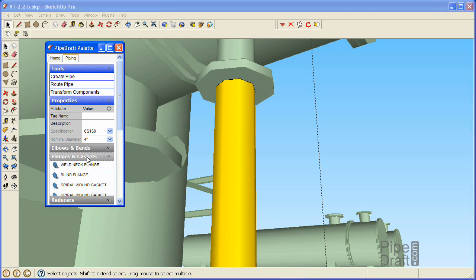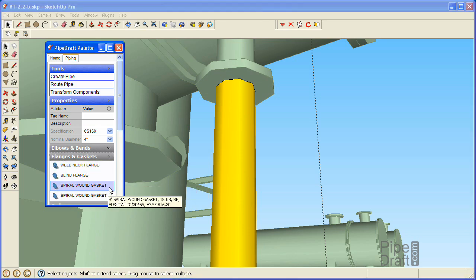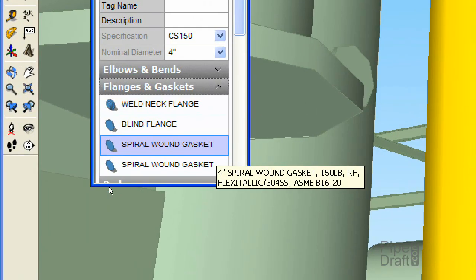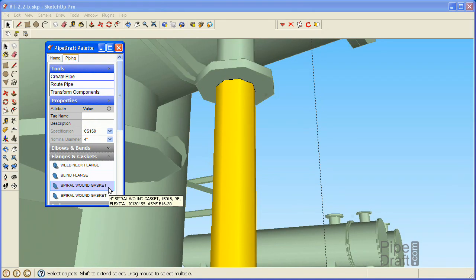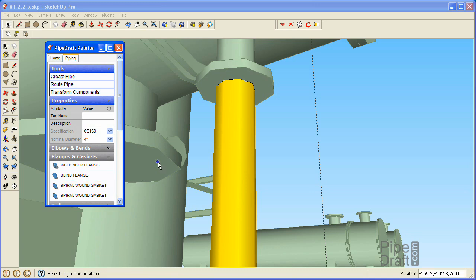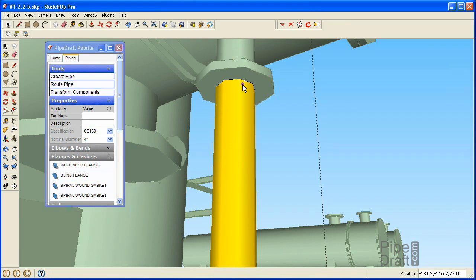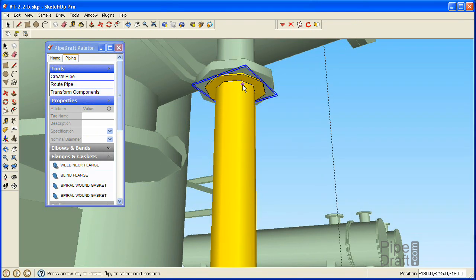Open the flanges and gaskets section of the PipeDraft palette to display the choices available in this size and spec. Click the gasket choice in the palette that is rated at 150 pounds, then click a position that is close to the end of the vertical pipe segment near the reboiler nozzle. We want PipeDraft to nibble away the pipe segment to make room for the gasket, which will also position it at the face of the reboiler nozzle.